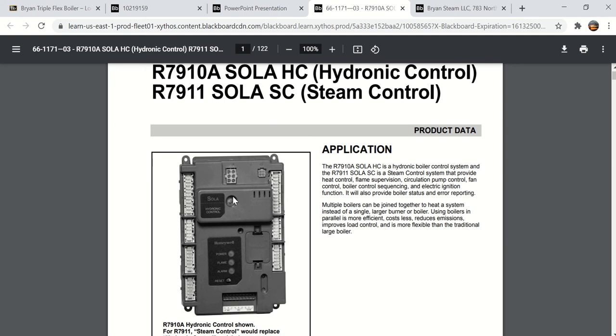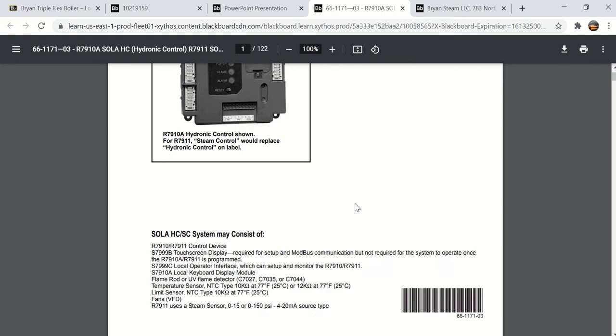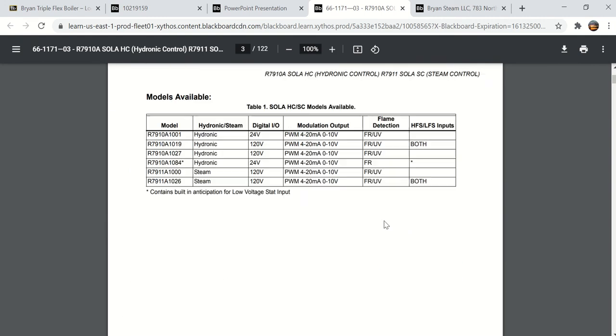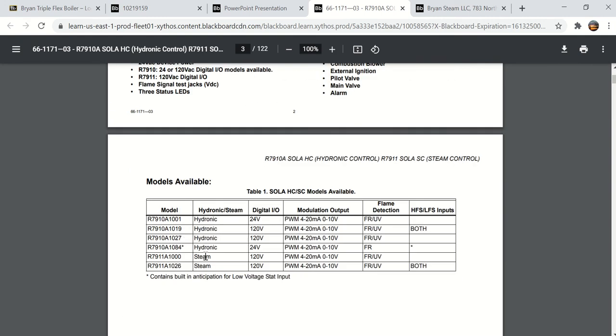They do that intentionally. The plug here, I think this was the plug for the pulse width modulation output, or maybe the UV scanner. Here is a terminal here if you're going to use the actual spark ignition transformer built into the controller for the spark ignition. There it is right there. They make 2 different versions of this. Here's the table. They make a hydronic version and a steam version. If it's a steam boiler, it's only available in a 120 volt model. For the hydronic heating or hot water boiler, you can get either the 24 or 120 volt.